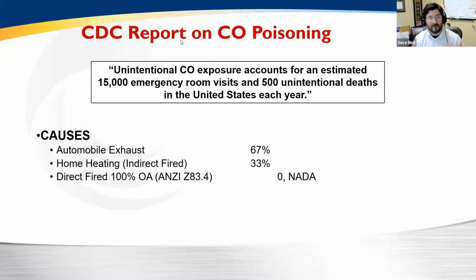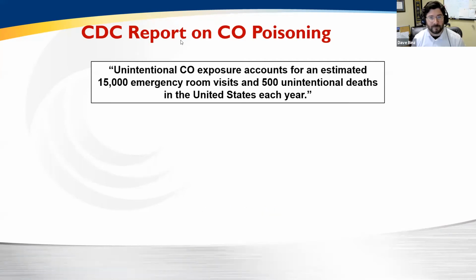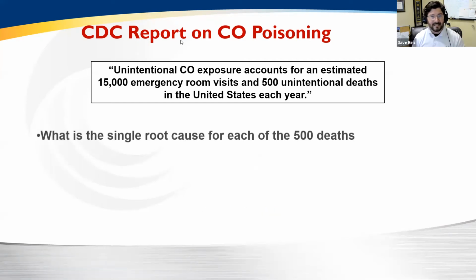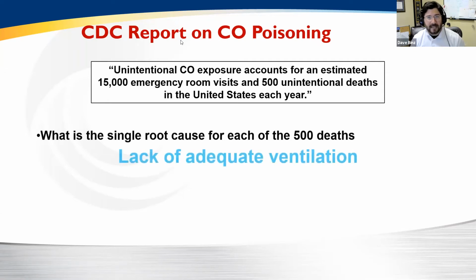And you may ask yourself, why? How can a technology that's designed to deliver the process of combustion actually be inherently safer than an indirect fired system? It ultimately comes down to what is the root cause of these CO exposures. And in all cases, the single root cause is lack of adequate ventilation. Whenever we have recirculating technology, really any indoor air pollutant, ventilation is the safety device. Dilution is the solution to pollution.